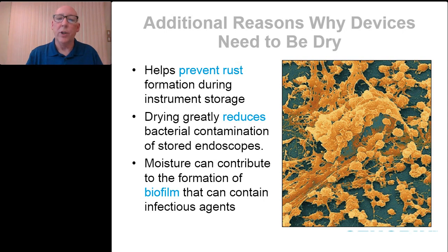Now, here are some additional reasons why devices need to be dry. The state of dry has a lot of benefits, which all relate to patient safety, no question about it. Improper drying can also cause water damage on devices. This can lead to discoloration, corrosion, rust, and pitting, making equipment unusable. So again, water, it's great for washing, right? Great for the ultrasonic cleaners, great for the washers. But we don't want that water to remain on devices because it can also cause issues with those devices themselves.